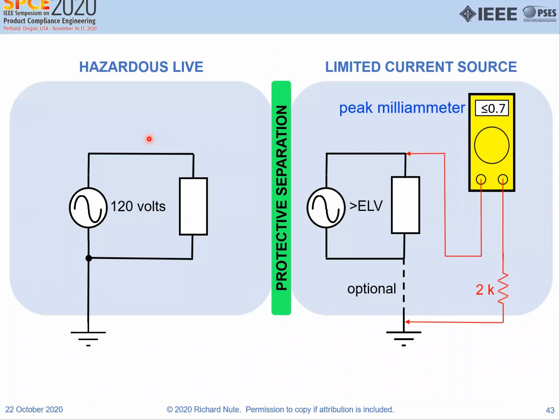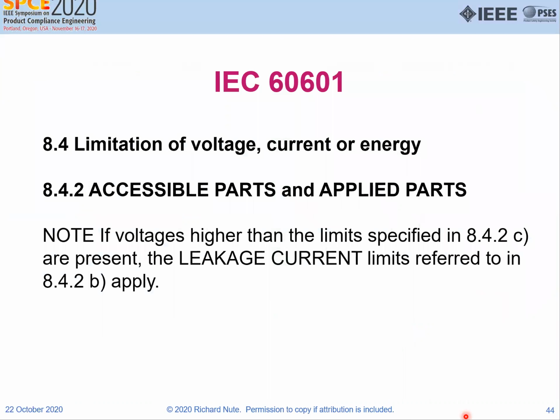So here's the hazardous live circuit we had once before. We have protective separation, and we have the secondary circuit, but this time the voltage is greater than ELV. So we measure this with the peak milliammeter, and it's 2 kiloohms. We put 2 kiloohms across this, and we measured the current. So let's look at what the standards say.